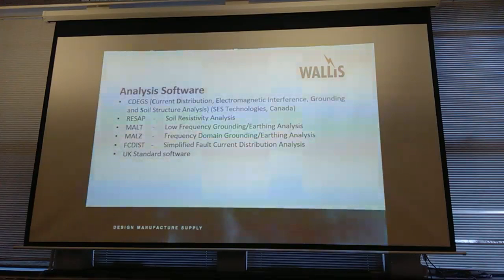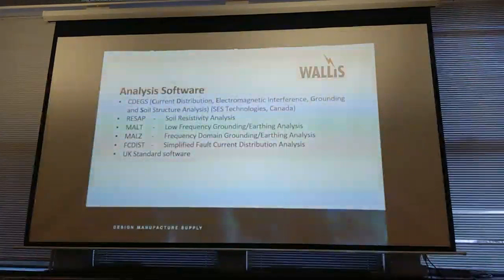We can then use either MALT, which is a nice simple module, and that is very good for, say, a GRP substation at the end of the road. It's very good for modelling that, and also if you've got a GRP enclosure substation and a metallic gas main running next to it. You can model the metallic gas main, and you can see what the transfer potentials are between the two. See if you're going to cause any problems to the gas distribution network.